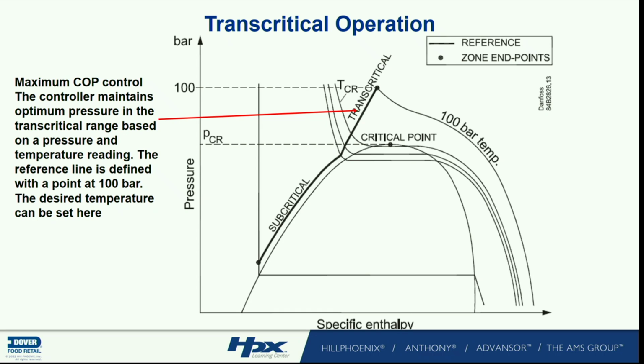That's why we're doing parallel compression. That's why we're doing ejectors. To get that percentage, take some of that mass flow off the compressors, change it to a higher saturated suction from the plus 20 to plus 38. So I can reduce the energy, yes? Yes. So that's what we'll work.